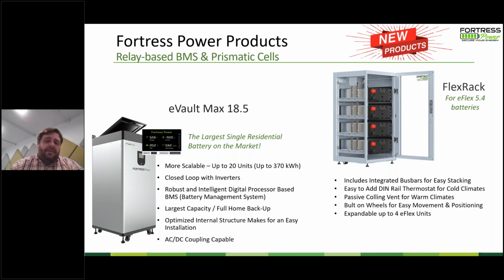The eVault Max does that as well as residential applications very well. So the eVault has some closed loop limitations. It really only supports the Sol-Ark and Schneider inverters up to 2 eVaults in parallel to get that communication between the battery and the inverter. You can have eVault projects that go up to 12, but they won't communicate directly to the inverter. It's all based on voltage.